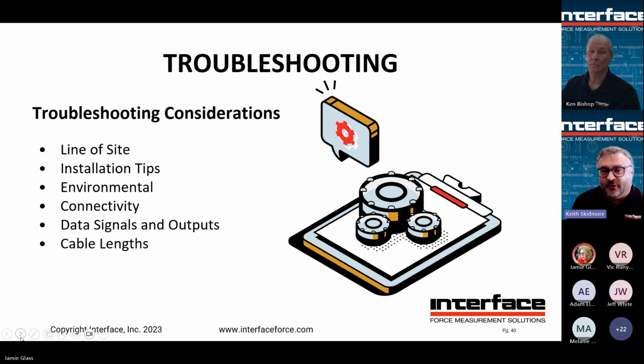We do have systems that can be used for site surveys. We have repeaters and things. So typically a wireless system can be made to work, but it may be important to do some surveying to make sure that you're getting strong enough signal at all the areas that want to listen to the signal. Installation, mechanical installation, is very important. They can be binding. You want to make sure that the load axis is through the load axis of the load cell. And sometimes if you have a load cell mounted, say on an I-beam, and you have a sling coming off it at some angle, the load isn't really pulling through the center of the load cell. So maybe it needs to have a rod end and a clevis, for example, so that the load cell can articulate and align. So again, if you're not getting good readings, it may be mechanical.